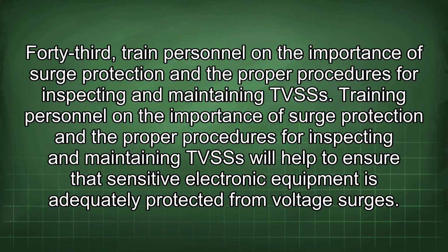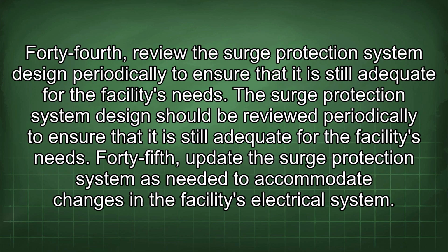43rd. Train personnel on the importance of surge protection and the proper procedures for inspecting and maintaining TVSSs. Training personnel on the importance of surge protection and the proper procedures for inspecting and maintaining TVSSs will help to ensure that sensitive electronic equipment is adequately protected from voltage surges. 44th. Review the surge protection system design periodically to ensure that it is still adequate for the facility's needs. The surge protection system design should be reviewed periodically to ensure that it is still adequate for the facility's needs.